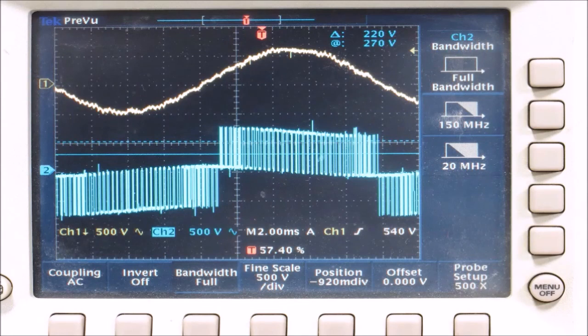The blue waveform is the square wave drive output and the yellow is the motor shield output waveform. You can see the motor shield filters the dv/dt voltage spikes and turns the motor input into a near sinusoidal waveform.